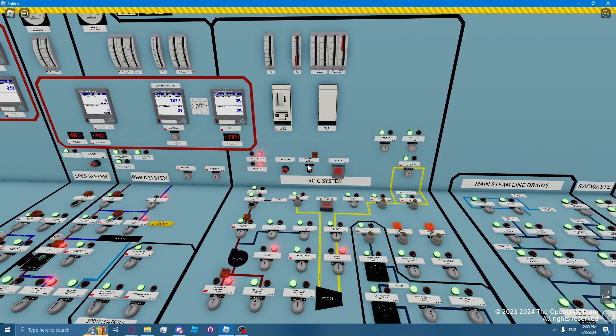However, the water-leg pump is powered by AC and is not battery-powered. During a station blackout, the RCIC system must be manually initiated by operators before the discharge pressure falls.